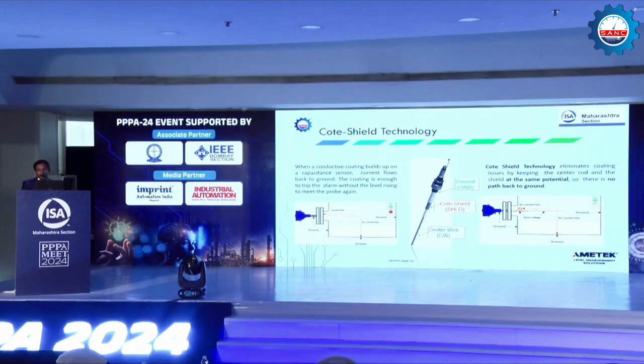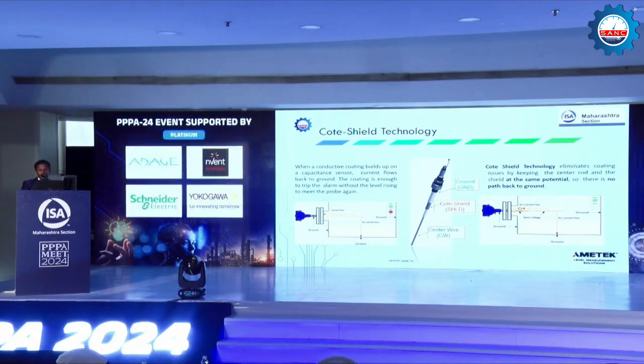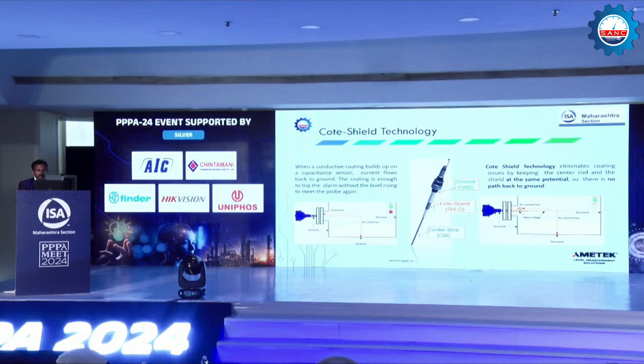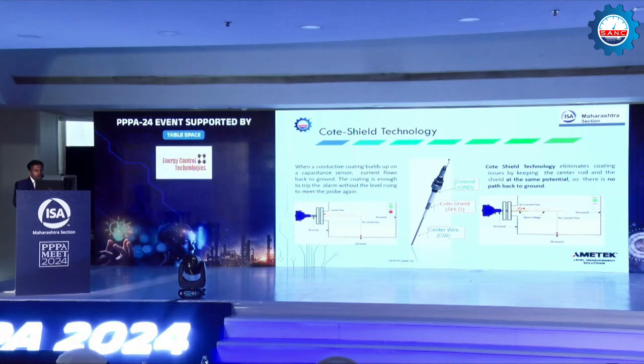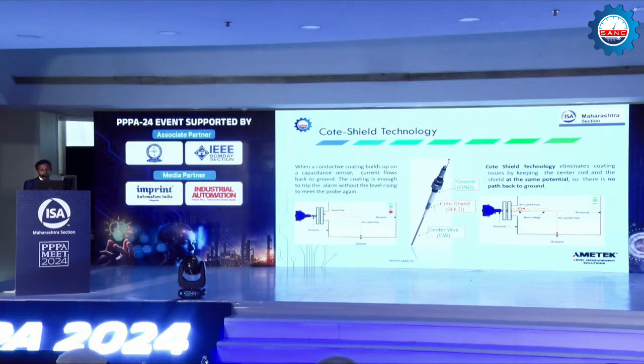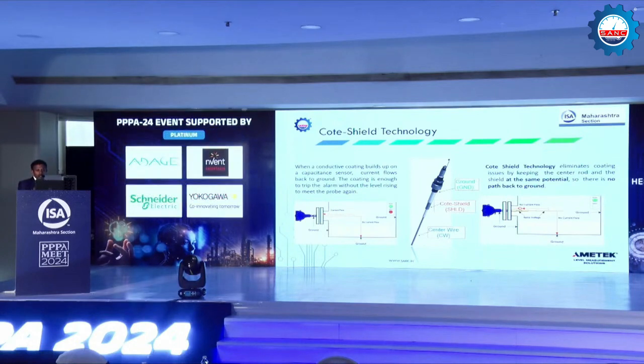The Cote-Shield, as the name suggests, is a shield against the coating. It is not done physically, it is done electronically. If you look at the Cote-Shield portion and the center wire portion, these are two independent probes, and we maintain the same potential at these two probes. When there is no potential difference, there will not be any current flow. So as the second picture shows, when there is sticky material left over on the probe, there will not be any current flow from the center rod to the ground through the coating. The current pathway will be from the sensor rod through the tank wall to the ground. So it always measures the actual level. It will not measure the sticky medium.